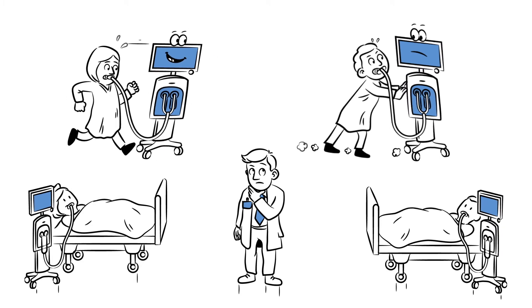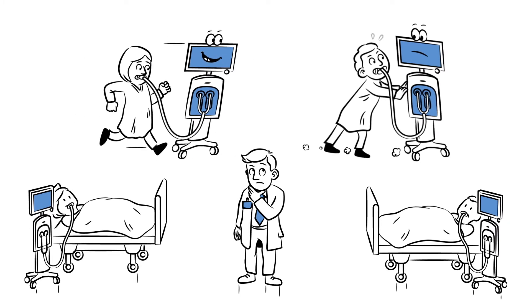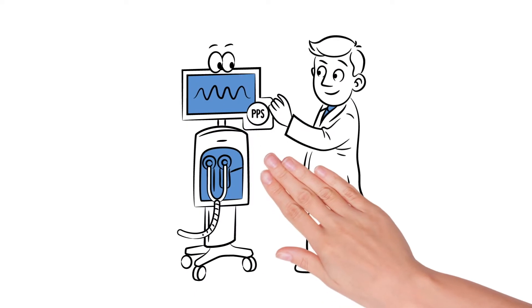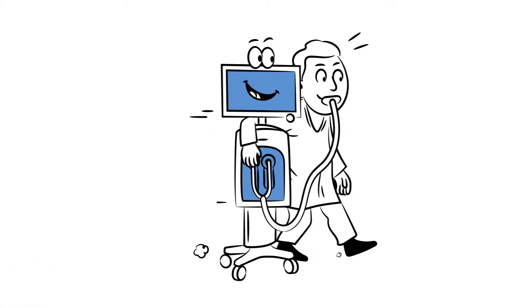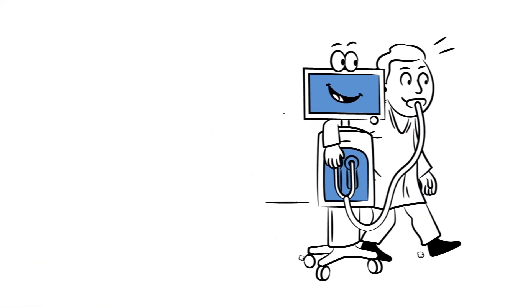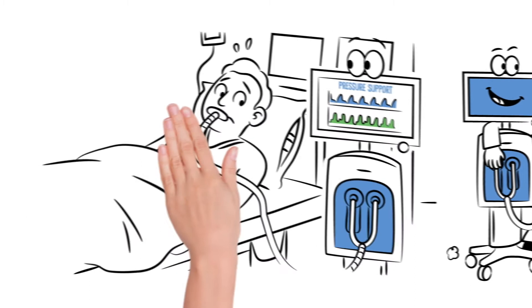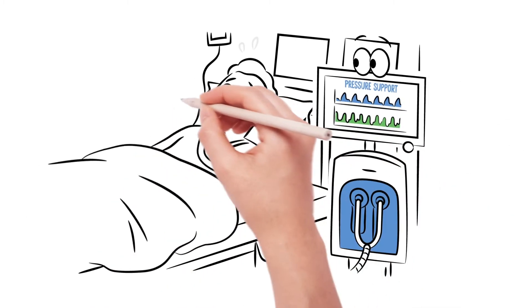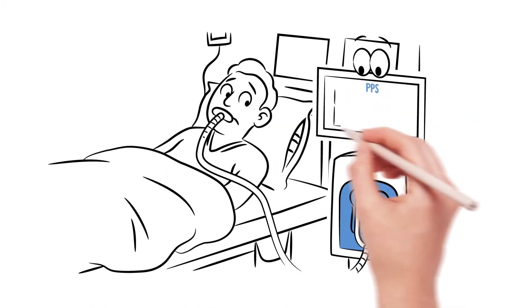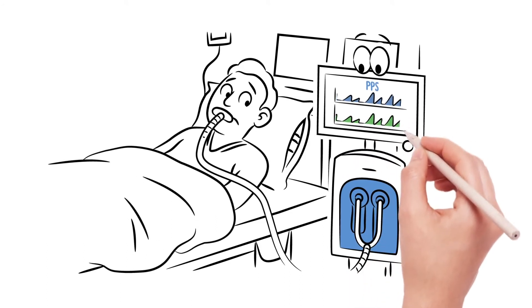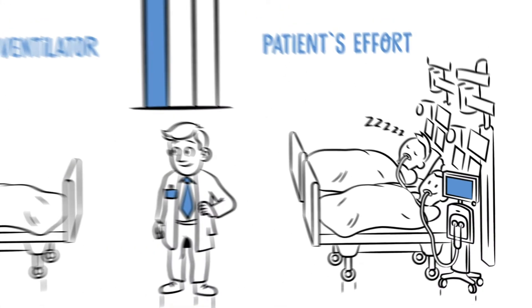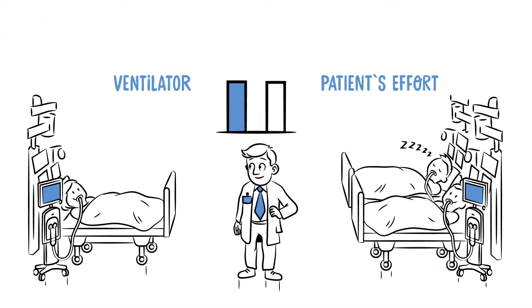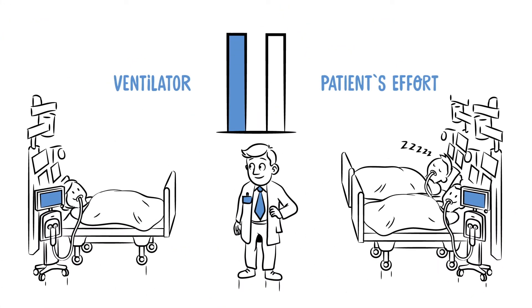Wouldn't it be great to allow the patient to take control of ventilation? Your patients can have this with proportional pressure support. It can optimally be adjusted to the spontaneous breathing of the patient. In proportional pressure support, the pressure delivered by the ventilator is proportional to the respiratory effort of the patient at every point in time. As such, it mimics a more natural form of breathing and gives patients a great deal of control.